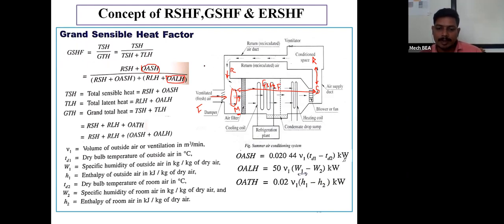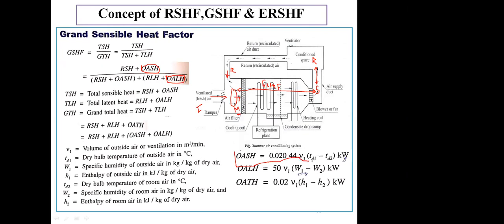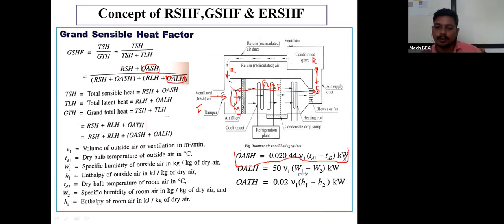Outside air sensible heat will be calculated by using the formula 0.02044 V1 (TD1 minus TD2) in terms of kilowatt, where V1 is the volume of outside air, TD1 is the dry bulb temperature of outside air or fresh air, and TD2 is the dry bulb temperature of the required room condition. And outside air latent heat will be calculated by using the formula 50 V1 (w1 minus w2), again in terms of kilowatt.